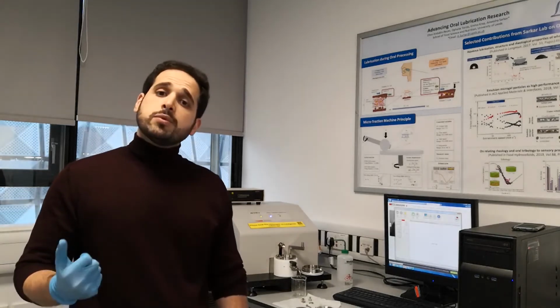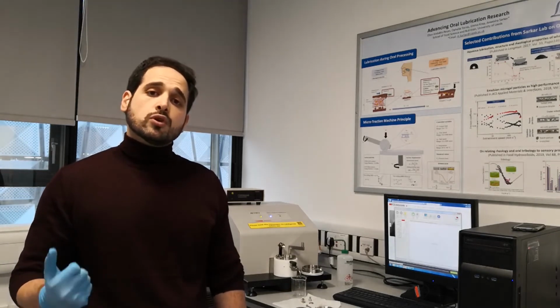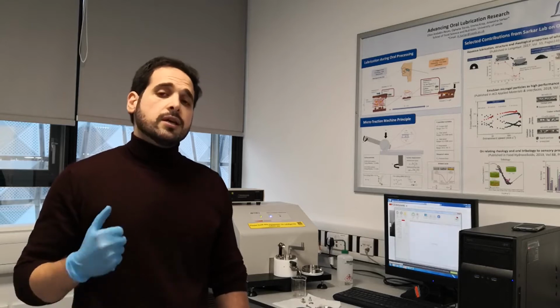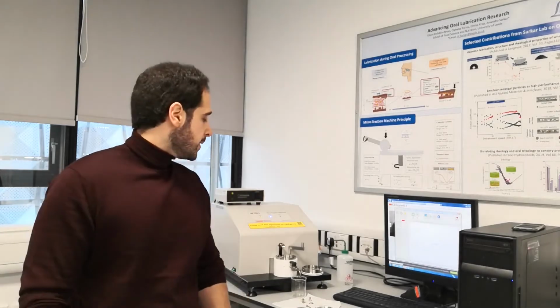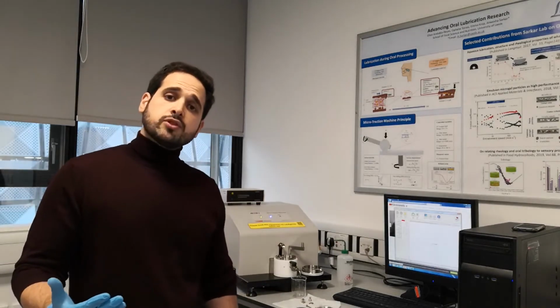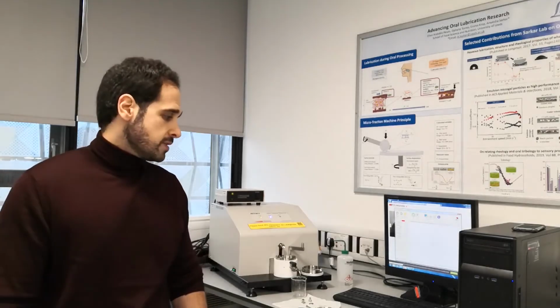And you can apply sliding rolling ratios of up to 200%. And you can also apply temperatures of a desired temperature you like, up to 150. But typically for all our oral tribology, we are applying a temperature of around 37 degrees.